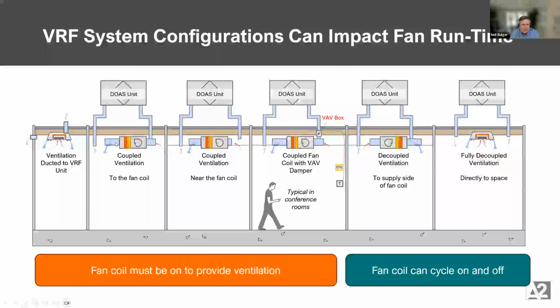So this slide has a lot of different configurations. We've kind of grown it over the years as we've seen different people design with VRF. But the point of this is looking at how the ventilation connects to that VRF fan coil and then the room, which can be rather impactful on fan energy for these different configurations. We'll have another concept diagram, but in some milder parts of California, we've even seen some very small schools just directly duct outside air to that unit. It runs all the time. It has to heat and cool all the air. It will not work in super cold climates, but it's very affordable, right? Very affordable. It also uses a lot of energy.